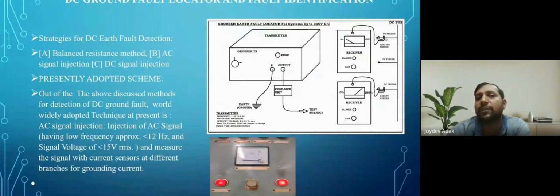This is the condition: these are the 3 DC feeders, and this is the DC bus. The test signal will be injected here. If a ground fault is there, say here, then the signal will flow through this path, through ground, and complete its path through this ground. The receiver will catch this signal and deflect, and it will show that the fault is in this feeder. In the other feeder there is no fault. If there is no fault, there will be no signal and no deflection in the receiver.